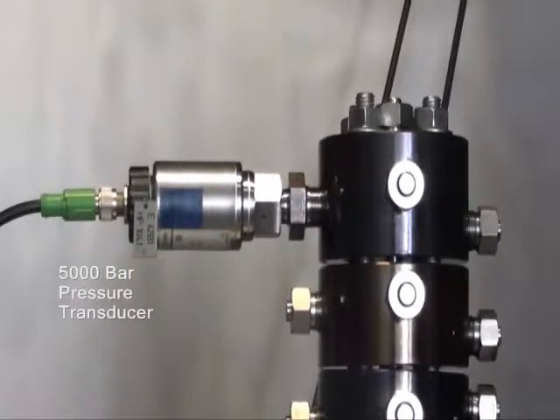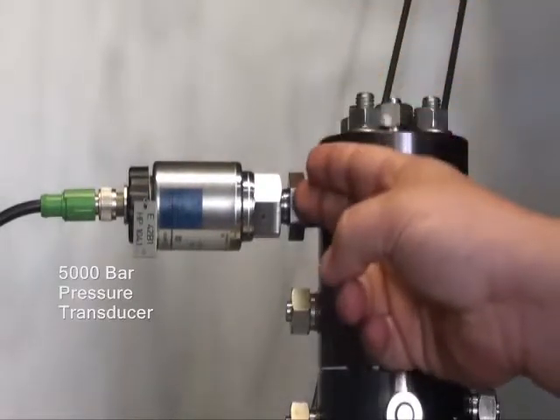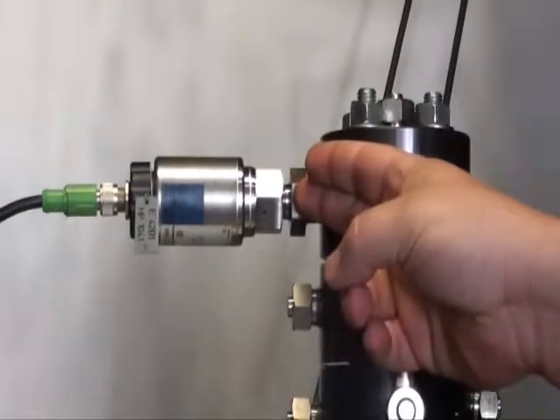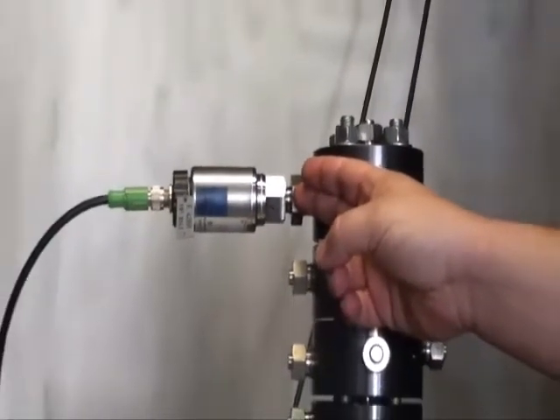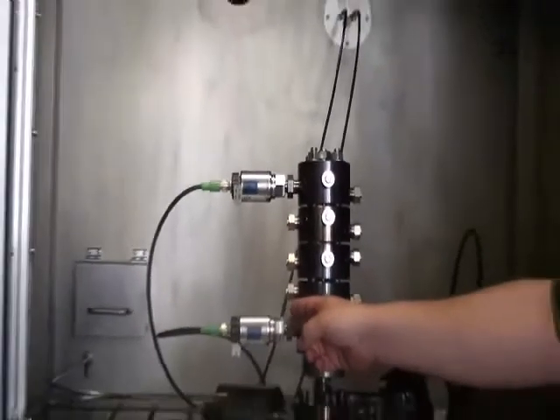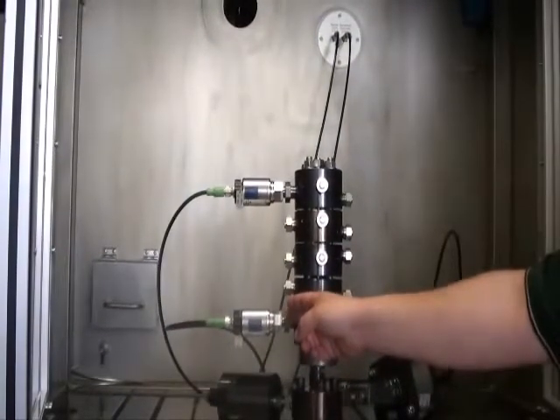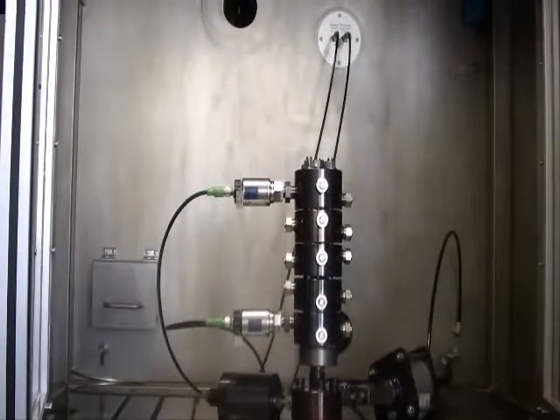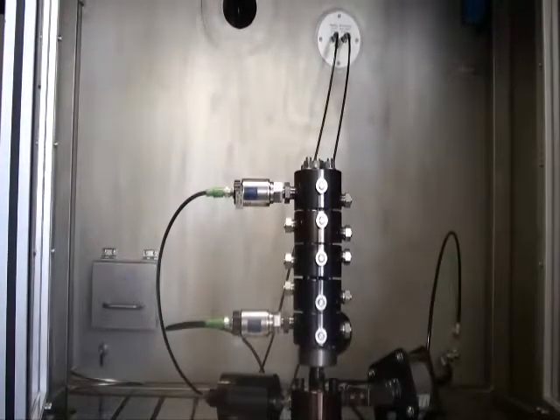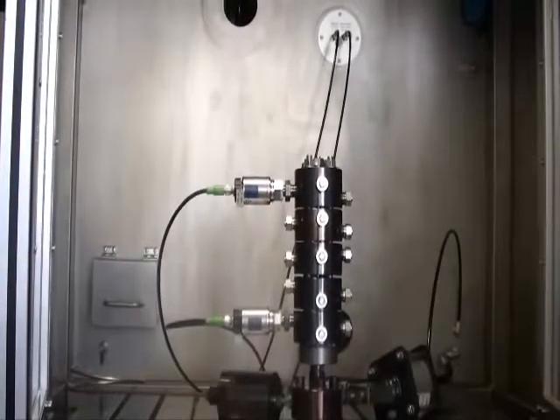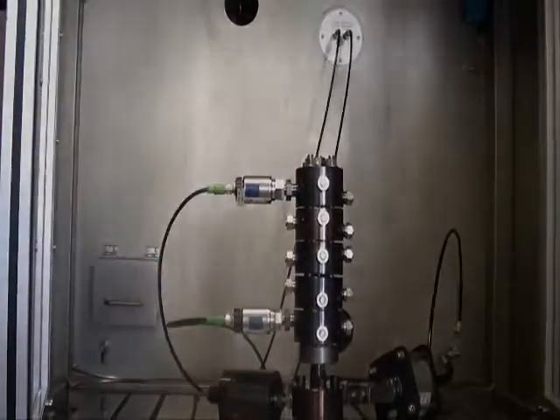On the test manifold you can see our calibrated 5,000 bar pressure transducer. This is how we measure the pressure to the test samples. In addition, Maximator installs a backup transducer. With this, we measure the pressure differential between these two transducers. If that differential pressure changes during the test, it'll shut down the rig. It'll indicate that we've got a failure of a transducer and shut down the machine. We're ready to go. Let's close up the doors and start up the test.